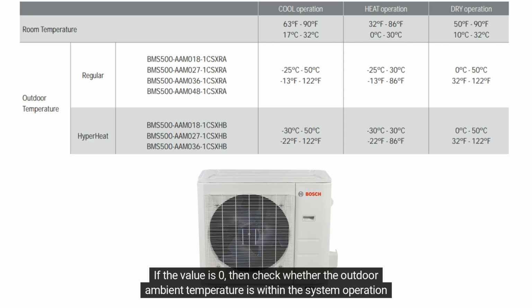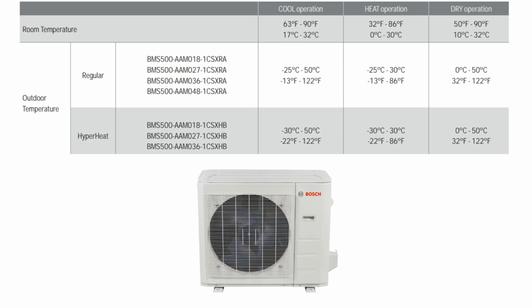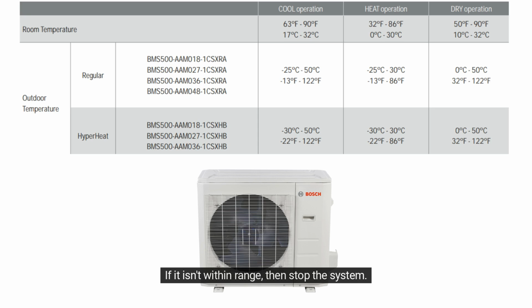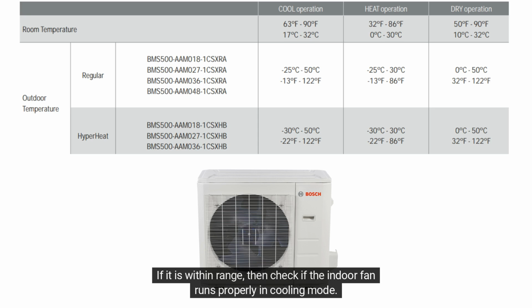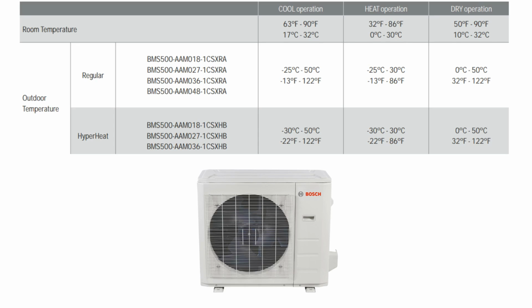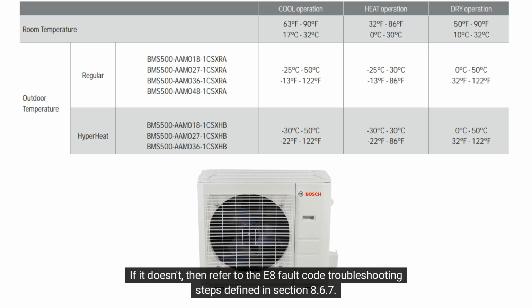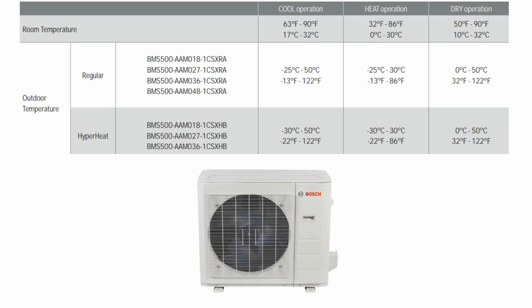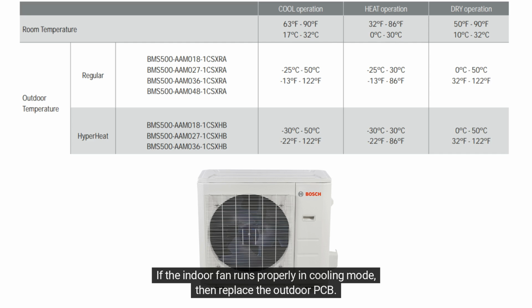If the value is 0, then check whether the outdoor ambient temperature is within the system operation range by looking at the chart. If it isn't within range, then stop the system. If it is within range, then check if the indoor fan runs properly in cooling mode. If it doesn't, then refer to the E8 fault code troubleshooting steps defined in section 8.67. If the indoor fan runs properly in cooling mode, then replace the outdoor PCB.